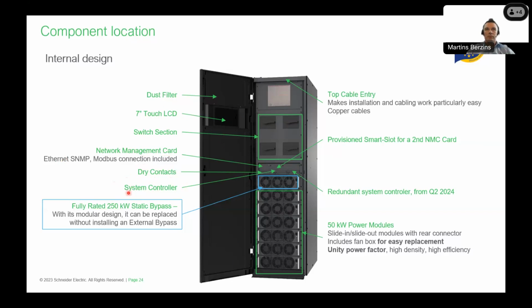So we have a system controller, and in Q2 2024 we will also have a redundant system controller. The system controller will be redundant and replaceable without interrupting the UPS work. The UPS has a fully rated system static bypass. It's rated to 250 kilowatts, and it also can be replaced without installing an external bypass. Cable entry for this UPS is from the top. We also have an accessory for bottom entry, which I'll show a bit later. Space for a second NMC card or network management card, and of course power modules of 50 kilowatts, slide in, slide out modules with a connection in the rear for easy replacement.